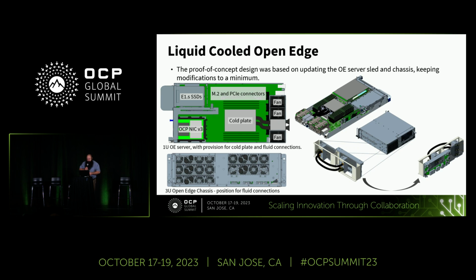This is sort of what the system would look like from the whole back of the rack perspective. The design was such that you would hook these up, so each sled itself is independently liquid cooled, and they would be pumped in parallel, so every one of them was kind of a separate standalone environment.